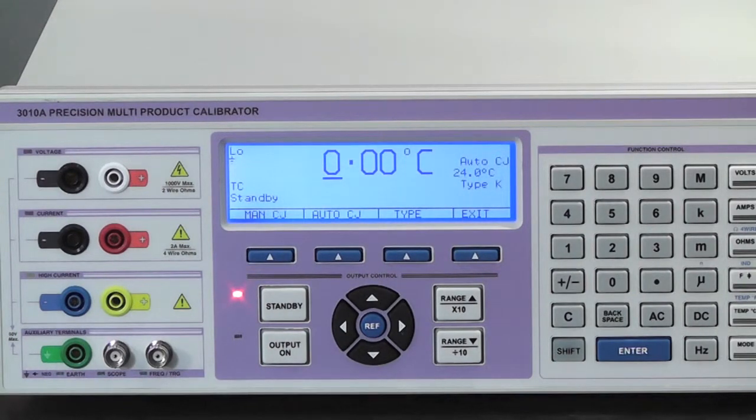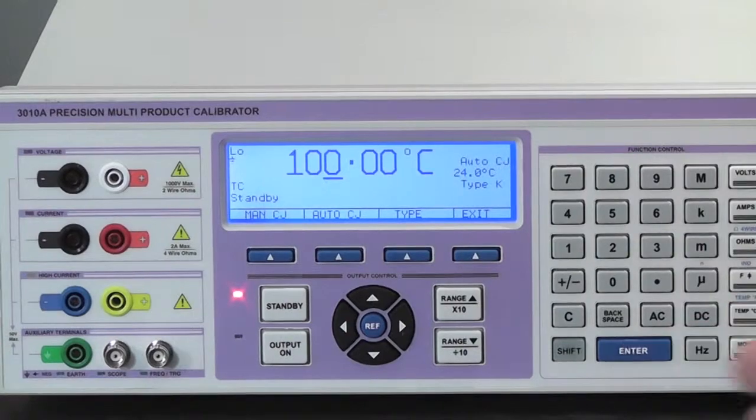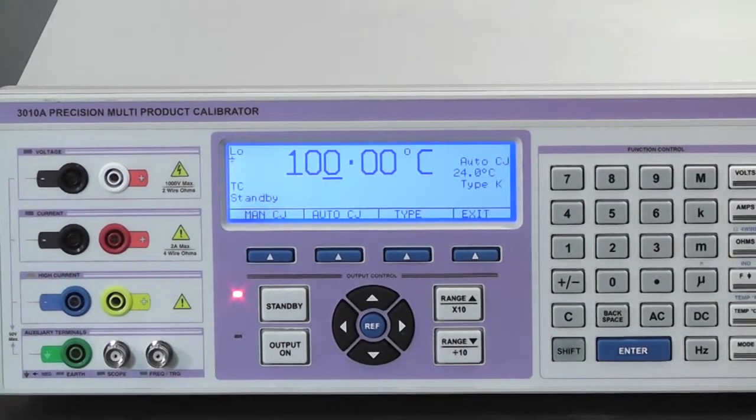Enter the desired temperature which can be anything between minus 250 degrees C to 1820 degrees C. For example 100 degrees C. Press the output on button.